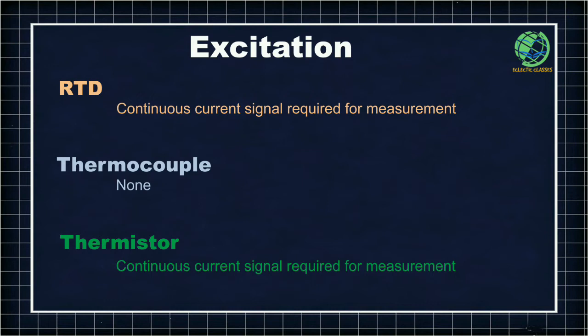In terms of excitation, RTDs always need a continuous current signal to measure temperature, as they change resistance with change in temperature. The same is true for thermistors, which also change resistance with change in temperature. That is not the case with thermocouples — since thermocouples generate a millivolt signal dependent on temperature change, no external excitation is required.